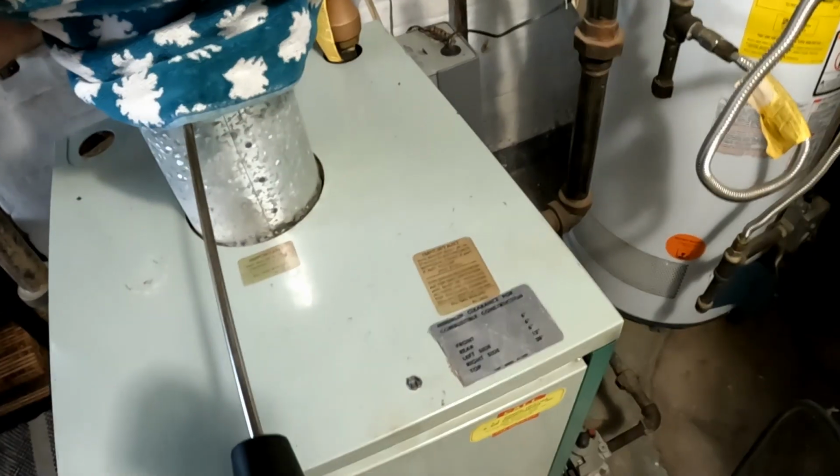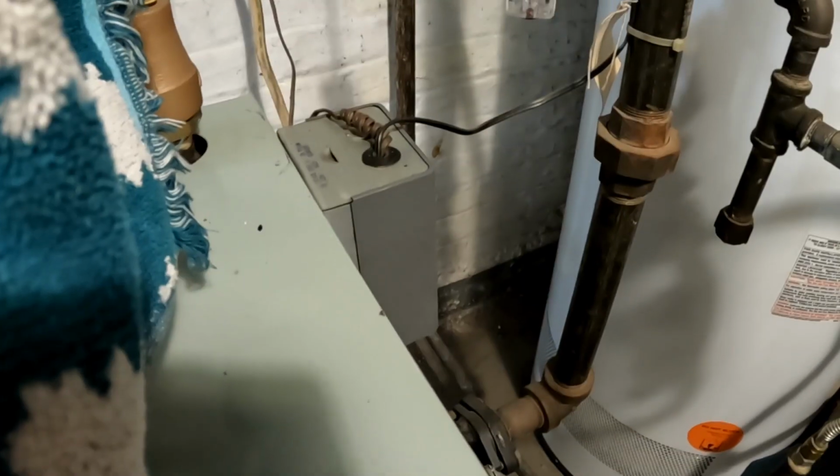By doing this, we're forcing the air to go down from the bottom of the board instead of up the draft hood, the dilution air. So the oxygen's going down in here. Okay, so you're about 1 second, moving the towel.